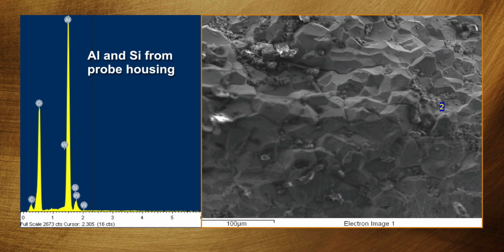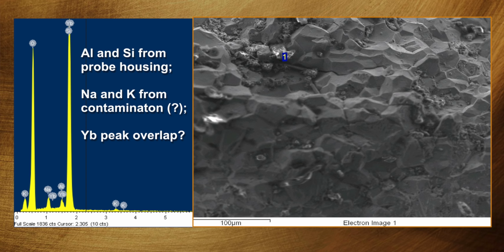Now in the same way, we can look at the tungsten probe tip. We look at the clean probe tip: aluminum and silicon, probably from the housing, right? It's got alumina around the actual metal. We also detect sodium and potassium. I put a question mark because that could come from contamination, or from whatever the preparation was. And then we have ytterbium. Terbium? That was also a shoulder peak on a few of these, so it might be peak overlap, or it could be real. We need higher resolution.